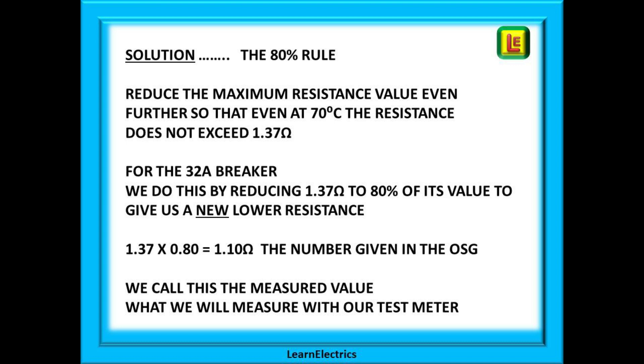Staying with our type B 32 amp breaker: if we know that at 70 degrees the resistance should not exceed 1.37 ohms, we can work backwards from 1.37 and find a resistance value at 20 degrees that guarantees that even at 70 degrees we will still have 160A of fault current. The factor to use is 0.8 — in other words, only use 80% of the 1.37 ohms. 1.37 multiplied by 0.8 gives us a new and finished value of 1.1 ohms, which we call the measured value.